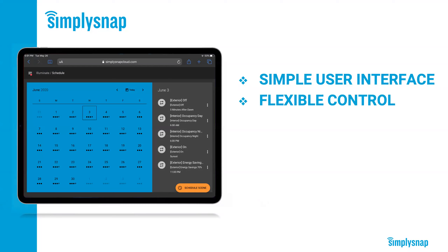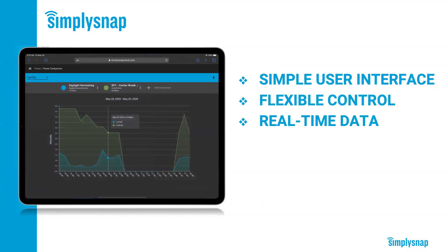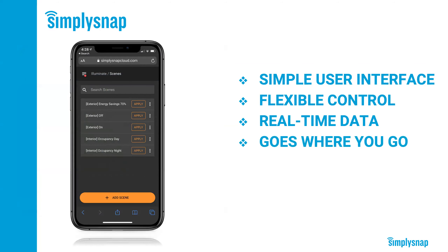The user interface has to be flexible. You can set up the lights to operate any way the customer wants — on a schedule, controlled by a sensor, or with customized push button control. Our users also want a user interface that updates in real time. You can always log in and see exactly what's going on with the lights and sensors and how much energy the system is consuming. This is what enables us to find problems — we can use the real-time power data to proactively send the customer an email if there's a problem with a light, whether due to a power issue or a hardware failure. And it works great from desktop as well as mobile.